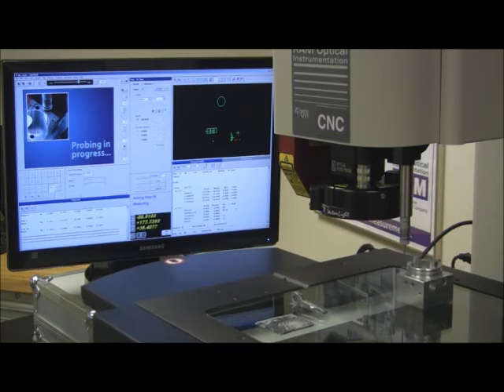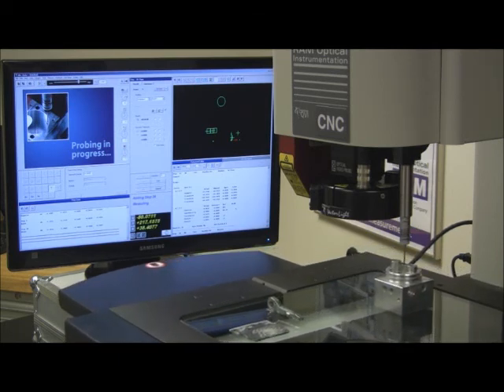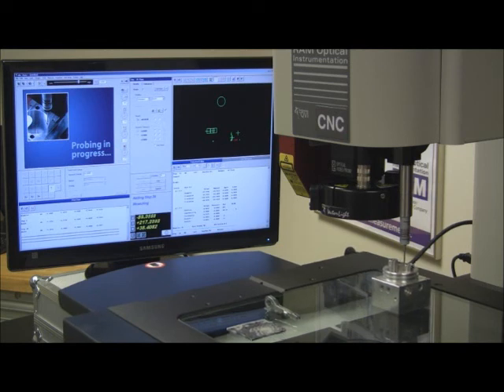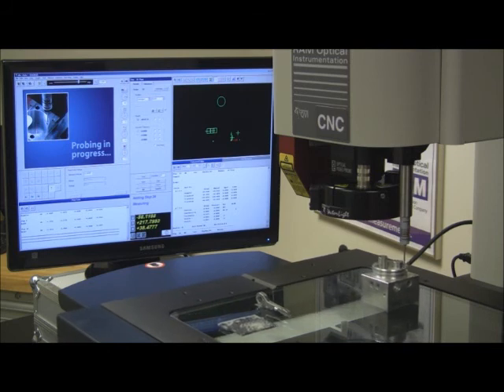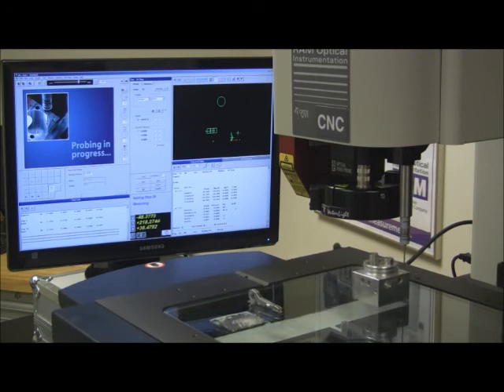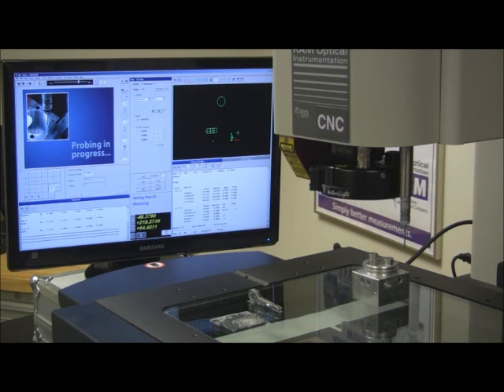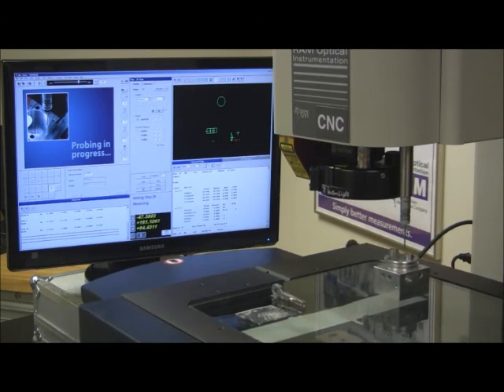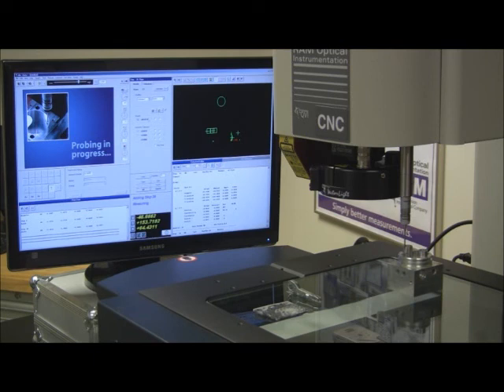And for this plane we'll measure 4 points around the outside. And I've got 1 more to go. I'm going to measure a line on the front, so I'm just moving the machine to that position before I stop. So I measured a plane, and at the 4 points, it told me the flatness was almost 2 microns for those 4 points.